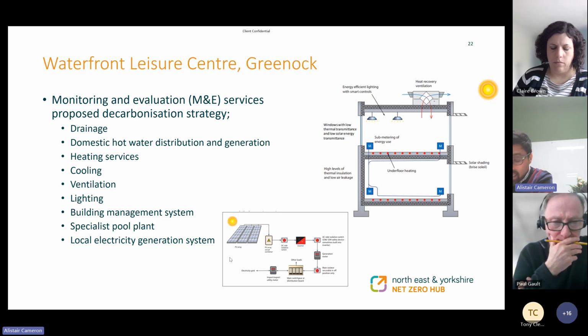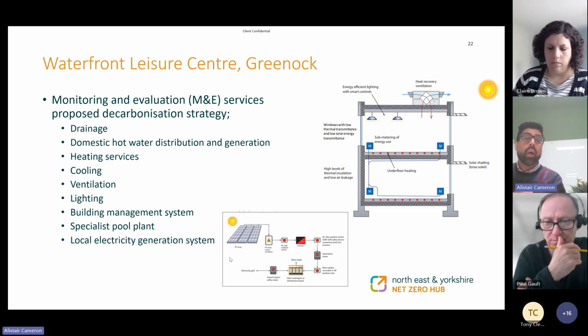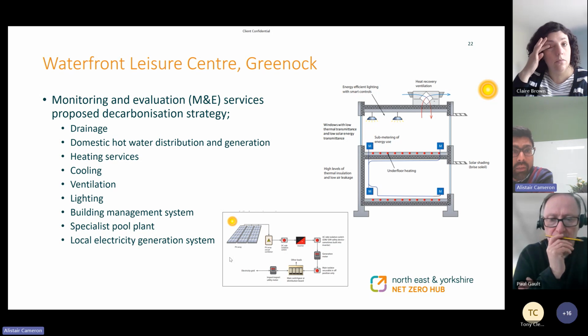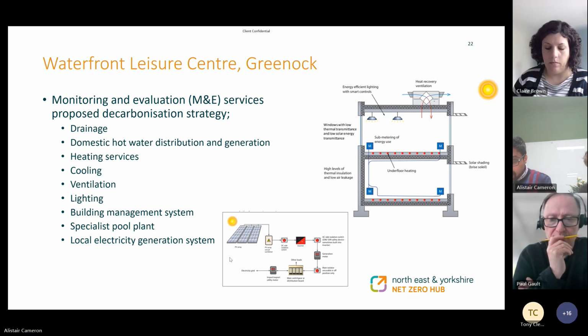And although we recognise that we do need to store hot water for a leisure centre where you've got lots of showers and lots of domestic hot water requirements, there are areas in the building where you could potentially take advantage of point of use electric water heating. For example, staff rooms, tea prep rooms, toilets that are away from the main changing village, they could essentially just have local hot water generation, and that would take quite a large amount of hot water distribution pipework off the system. And we by default benefit from the energy savings associated with that reduced distribution loss. The heating system at the moment, it is gas boilers.